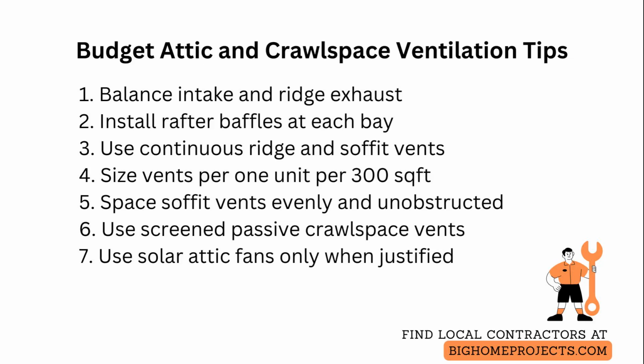For crawl spaces, use screened passive vents positioned for cross ventilation and place them near the lower side to take advantage of prevailing wind and pressure differences. Raise the vents above soil grade and consider adding a vapor retarder on the ground to reduce evaporative moisture.